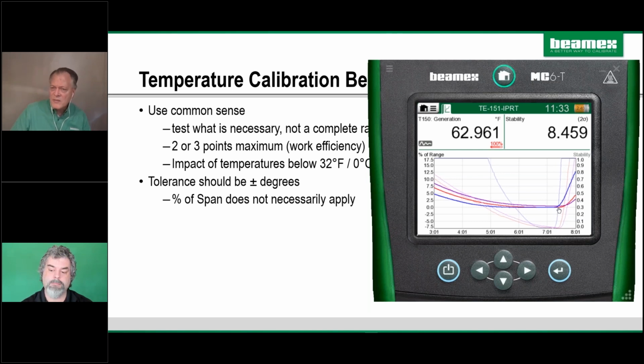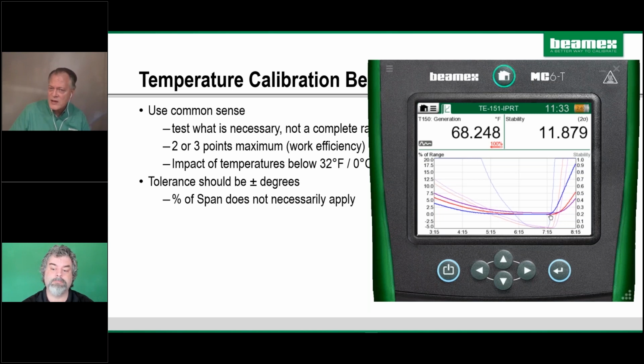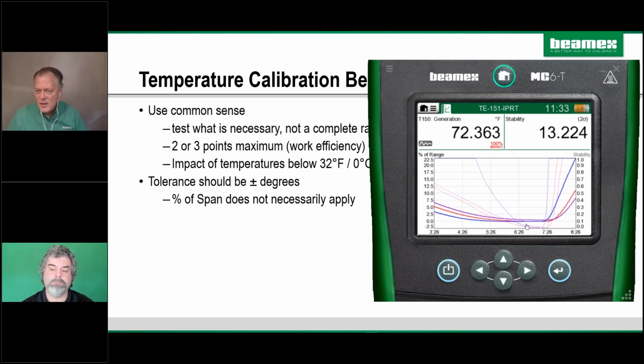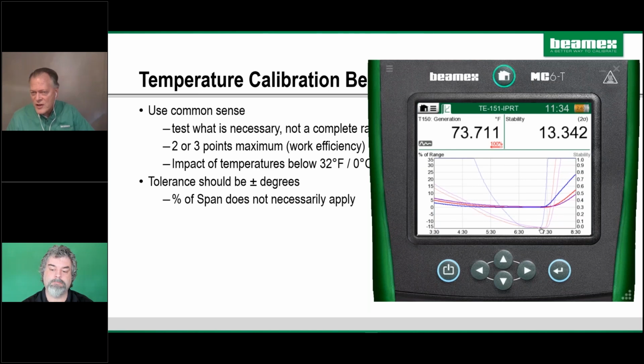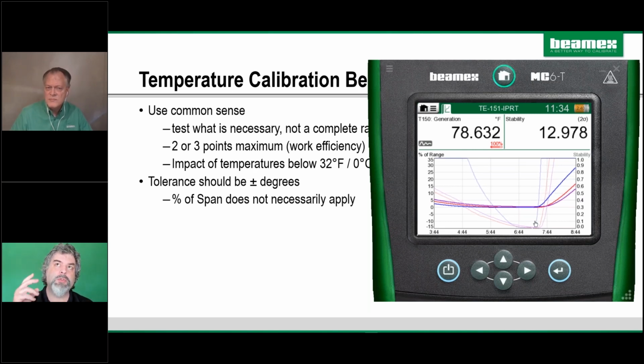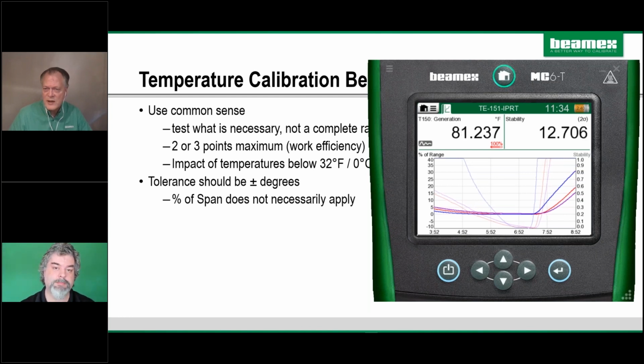But that was pretty quick, Roy. Yeah, we've been practicing this, and we turned that stability check off. I think it did speed things up. So you can control when the log takes place. So if you want additional delay, all dry block people allow you to dwell a little bit longer if you want to. But our point is look how stable the sensors were when we took the reading. They were all together, so waiting additional time really wouldn't have gained you anything. And part of the point here is that the end goal is for you not to have to babysit this test, that you press start and you walk away.